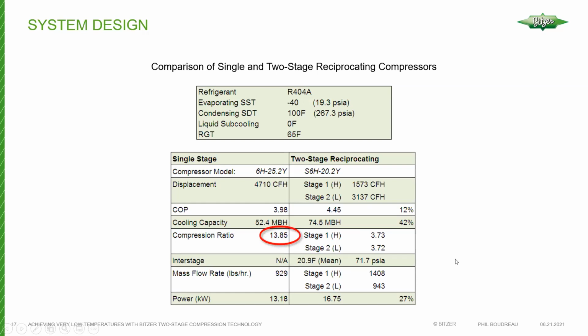Then we have the compression ratio. A single stage would be 13.85, whereas each stage in the two stage operates at 3.72, 3.73. Nice and low. Lower compression ratio always results in a higher flow rate through those cylinders and higher efficiency, more bang for the buck, basically.